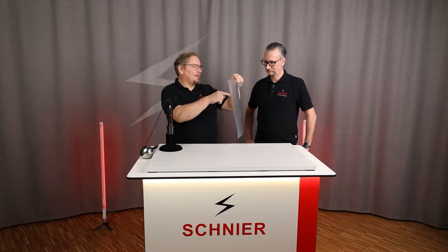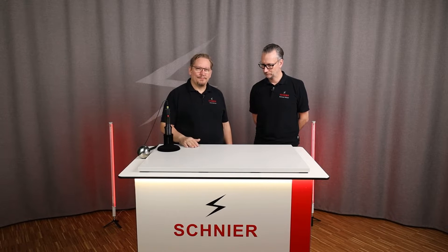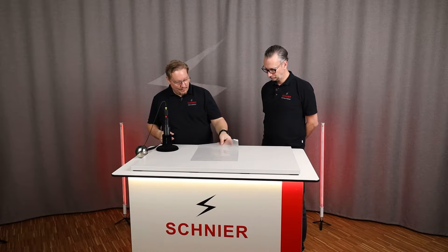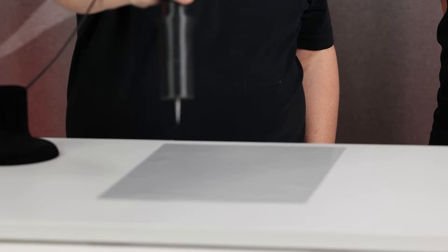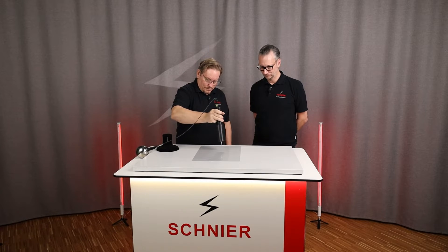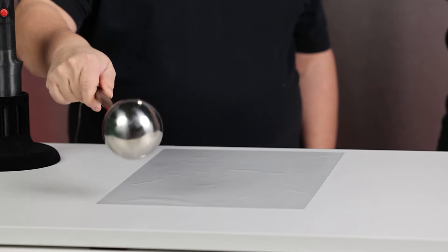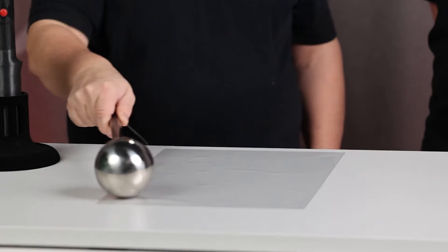The electrons tend to go over to me — I noticed on my shirt how the charge goes in my direction but not forwards. It is completely different when I place the foil on this grounded plate, and this is exactly what happens relatively often when painting. There are some conveyor systems that are protected with metal plates, and to make these metal plates easy to clean you simply stick a film on them. But when we spray with electrostatics in the paint shop — with high voltage — I take the foil, place it here, go over it with my high voltage generator, and you can really see how the foil is sticking. And when I come back with my grounded ball, there is a lot of electrostatic charge on it.